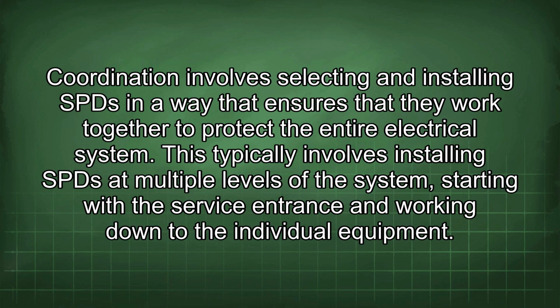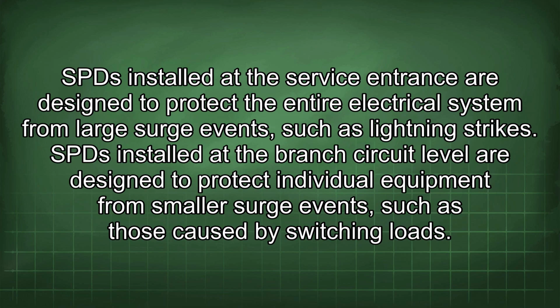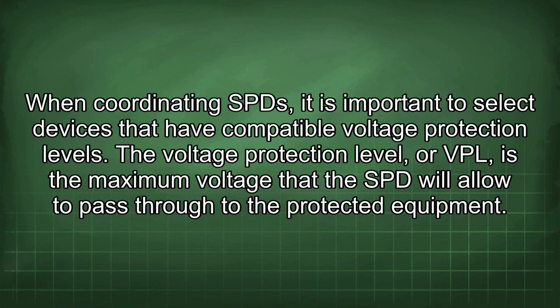Coordination involves selecting and installing SPD in a way that ensures that they work together to protect the entire electrical system. This typically involves installing SPD at multiple levels of the system, starting with the service entrance and working down to the individual equipment. SPD installed at the service entrance are designed to protect the entire electrical system from large surge events, such as lightning strikes. SPD installed at the branch circuit level are designed to protect individual equipment from smaller surge events, such as those caused by switching loads. When coordinating SPD, it is important to select devices that have compatible voltage protection levels.